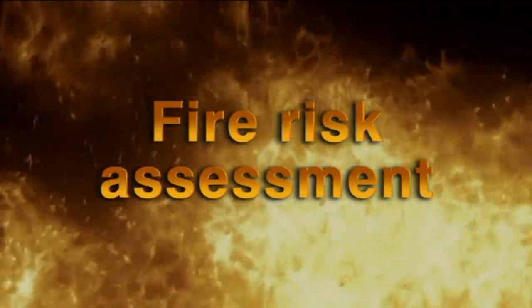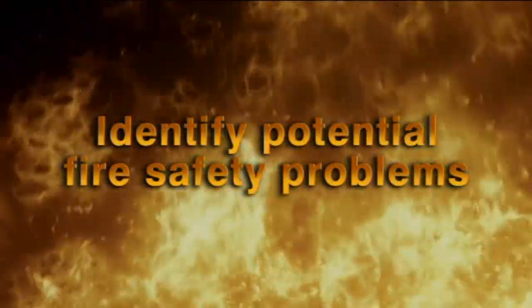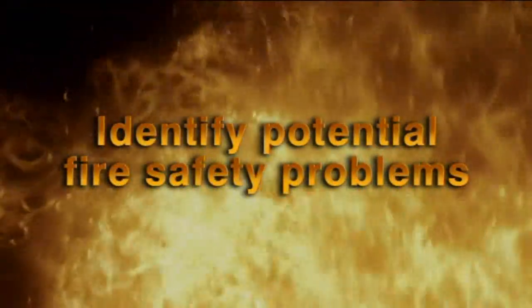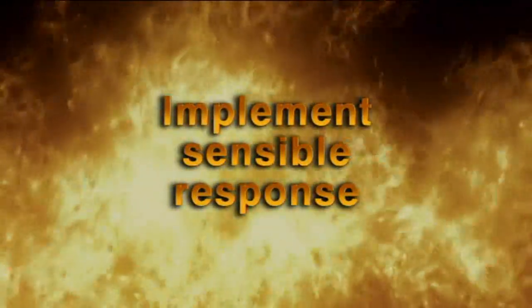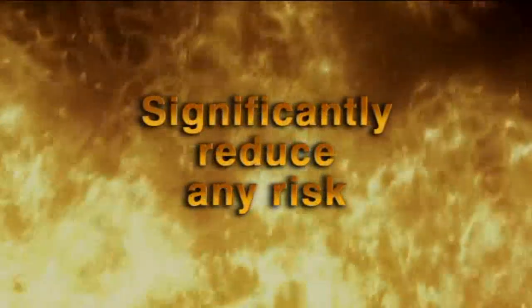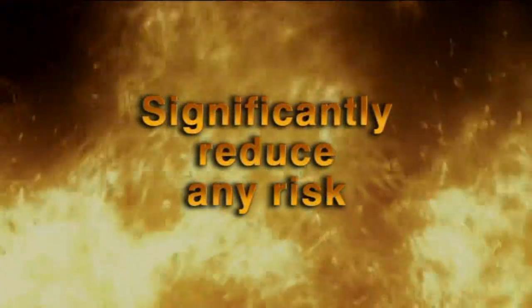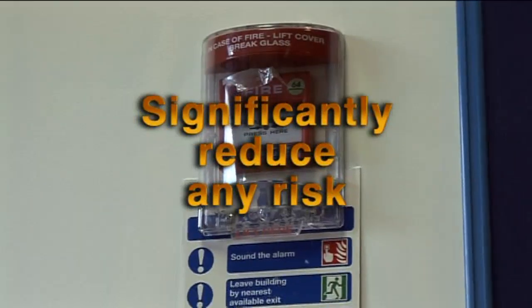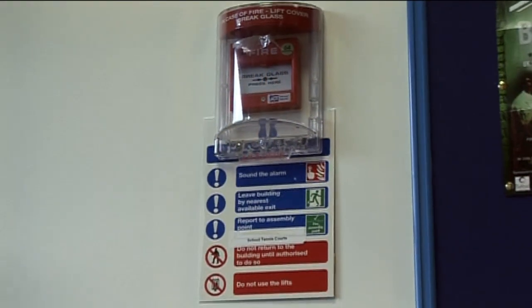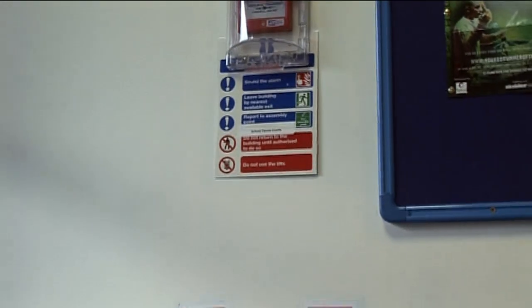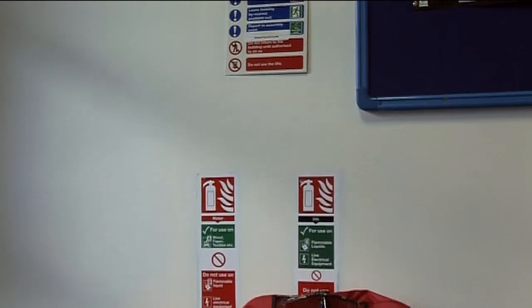So, what is a fire risk assessment? The aim of a risk assessment is to identify potential fire safety problems, decide how serious any problems found might be, and do something sensible about them. Where possible, this should eliminate the problem or at least alter it enough to significantly reduce any risk. This can usually be achieved by providing an appropriate mix of physical fire precautions and suitable management processes.